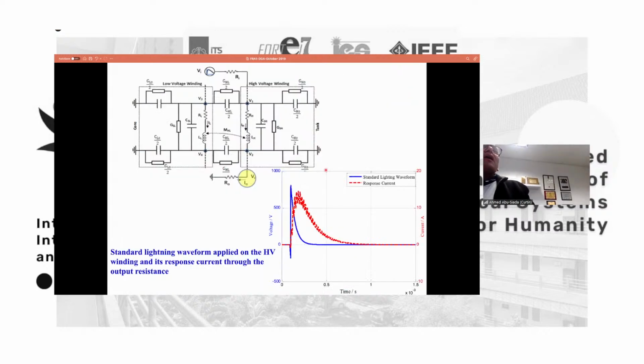Some other people asked, how about if during transformer operation I connect an impulse generator? I only need maybe 1 kilovolt or 500 volts for a few microseconds. Can I connect it to the operating transformer, for each phase, and plot the FRA? So what they did was connect an impulse signal like this through an impulse generator, and measured the impedance or admittance, or transfer function, against frequency.